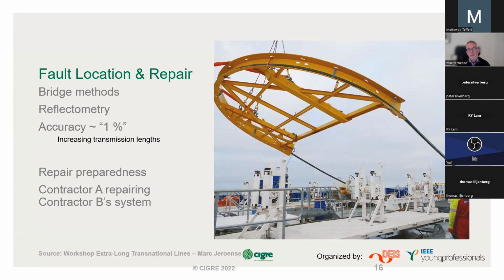The two important messages here are that nowadays fault localization accuracy involves two steps: first a coarse localization, then a fine tuning. The first step, the coarse localization, typically has an accuracy of about 1%. If I talk about future increasing lengths, say a transmission line of 1,000 kilometers, that's 10 kilometers for my first estimate, which is still quite some length.